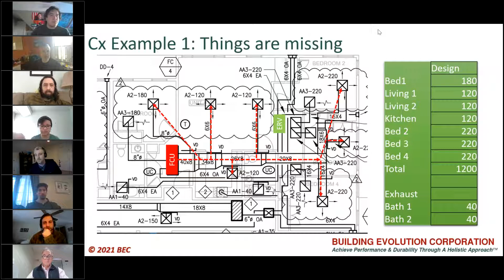And look, we found the duct. So here's the mysterious duct that we're trying to find. Well, we were able to drill a hole in it, and through that hole, we could then put the borescope and feed it down the duct line and find that they didn't have turning vanes in the actual 90 degree.